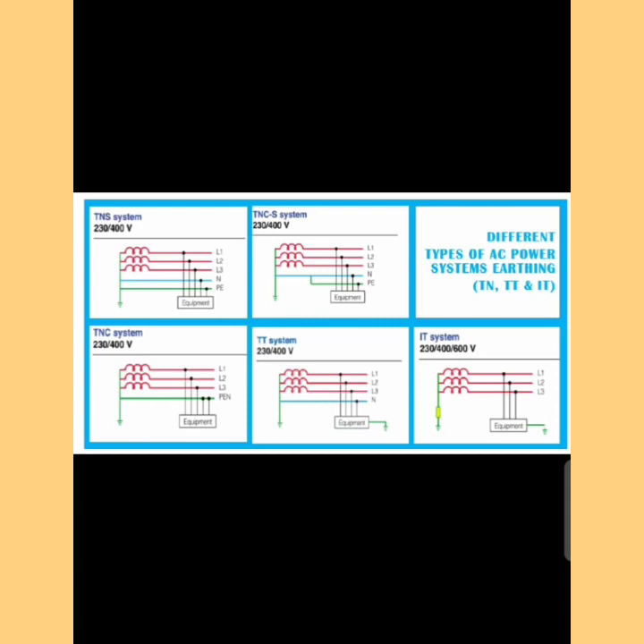In the TT system, both the load and the source are connected to ground independently — they are not connected together. In the IT system, I stands for isolation and T for Terra (earth). It is an ungrounded system, and at the load, equipment is grounded independently through a dedicated earth. This was the small information.